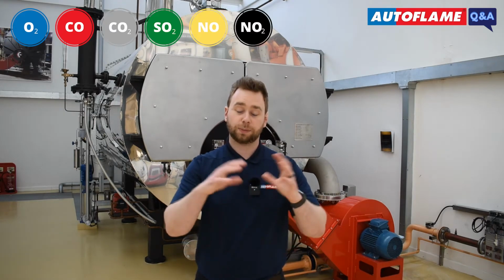The EGA is designed to help businesses measure and report their environmental impacts, including greenhouse gas emissions. Understanding and reporting these emissions can help identify ways of improving environmental performance and cutting costs. The EGA is capable of continuously measuring your O2, CO, CO2, SO2, plus your NO and NO2, which makes up your NOx emissions. This data is calculated together with your exhaust gas temperature and your ambient air temperature to produce a real-time audit of your greenhouse gas emissions.